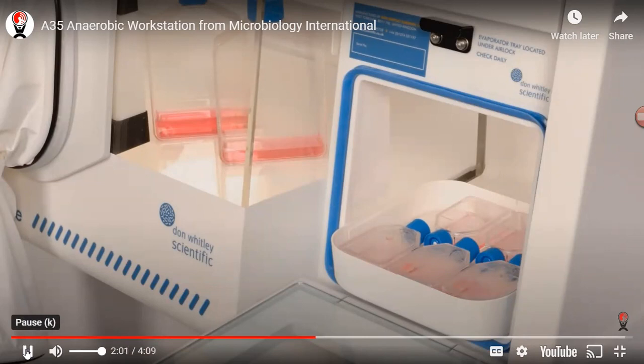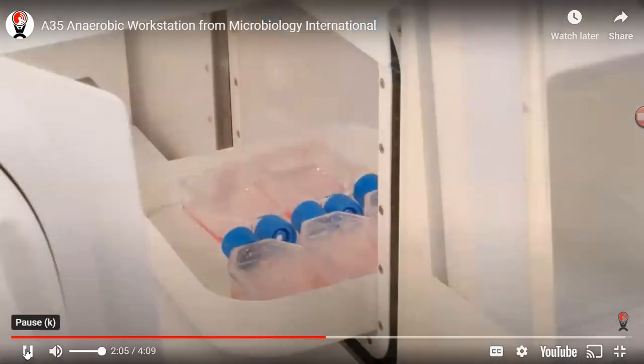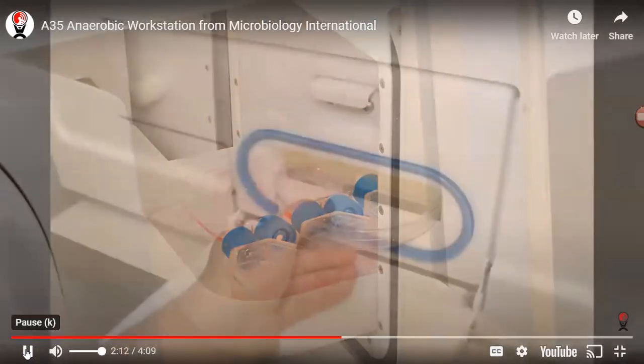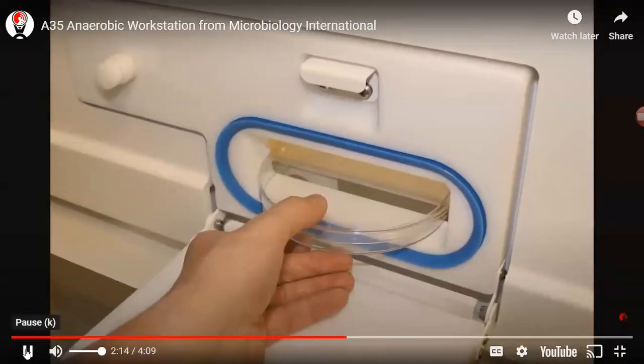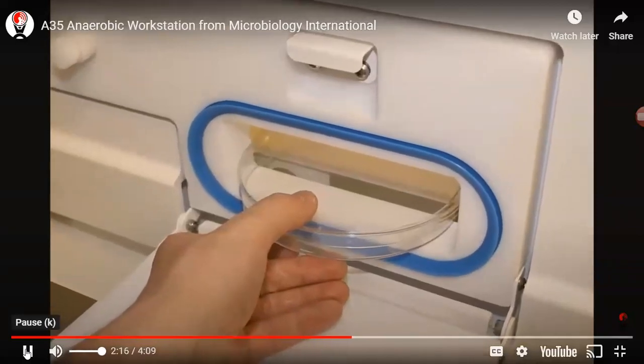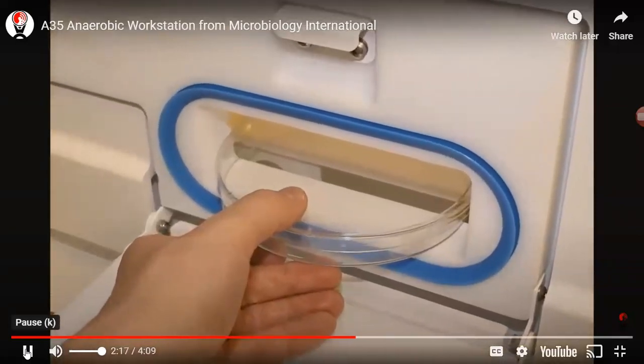The A35 is equipped with a transfer airlock to introduce samples or equipment. The 12-liter rapid cycle airlock has the capacity to introduce up to 40 petri dishes in 60 seconds. There is also the option to specify the 15-centimeter letterbox, ideal for quickly transferring all sizes of dishes and small items. Operating the airlock is very simple.